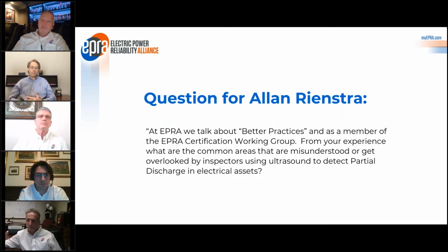For contact inspections, the biggest mistake I see is people ignoring what we call acoustic impedance. Acoustic impedance is basically the equivalent of electrical impedance. It states that an ultrasound signal traveling through a solid medium, whether steel, copper, or whatever, is traveling through a medium.